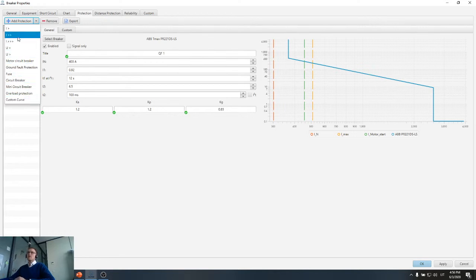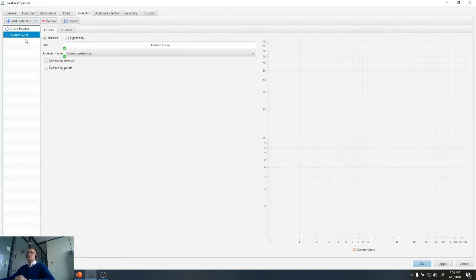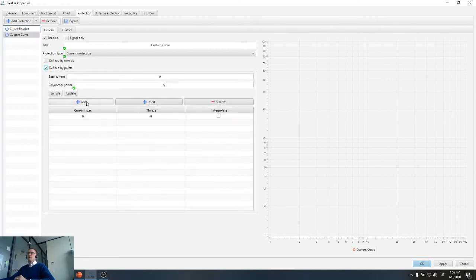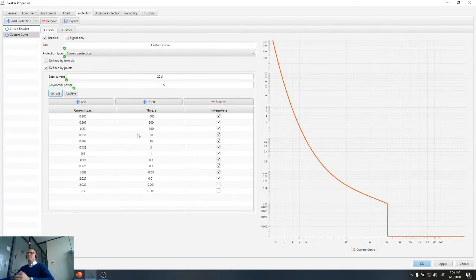And if there is some protection device that we don't have in the software, we provide custom curve functionality, where the user is capable of specifying the TCC curve by hand and including this kind of protection device in the calculations.